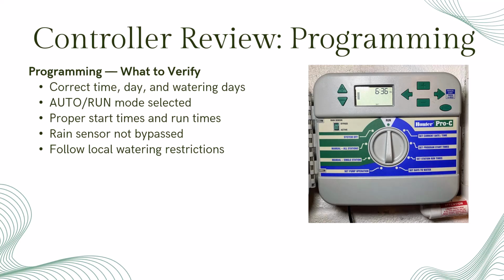Once the controller passes the physical inspection, I review the programming. First, I confirm the current day and time. Mechanical clocks will always drift a bit, but they should still be close. Then I check the watering days. In Florida, that means no more than 2 days a week in summer and 1 day in winter, unless it's a drip zone, which is exempt. This is where systems often fall out of legal compliance. Next, I confirm the controller is set to auto or run. Some homeowners turn it off between waterings, especially retirees who only run their system manually, so I make note of that if it applies.